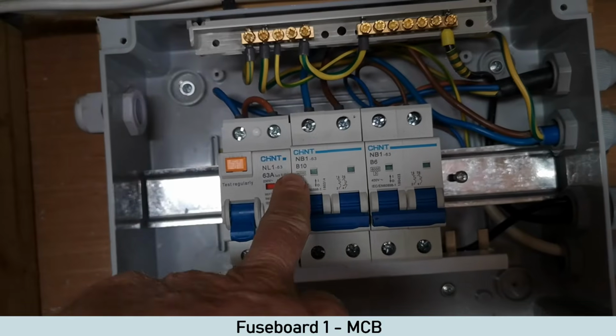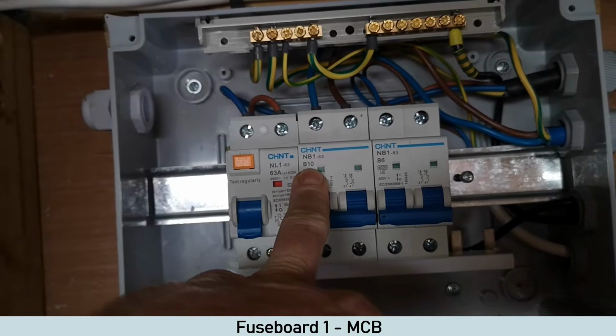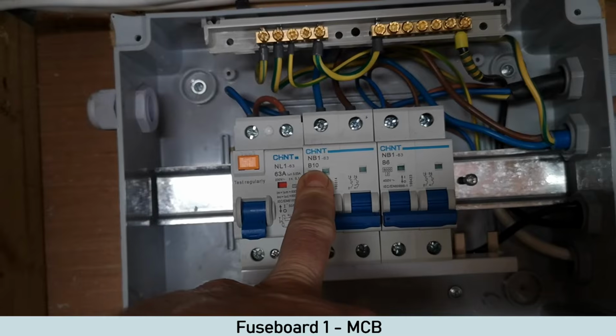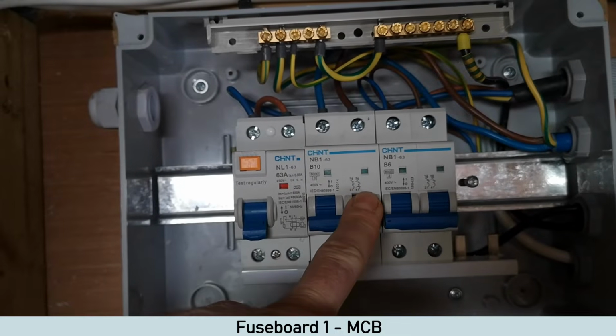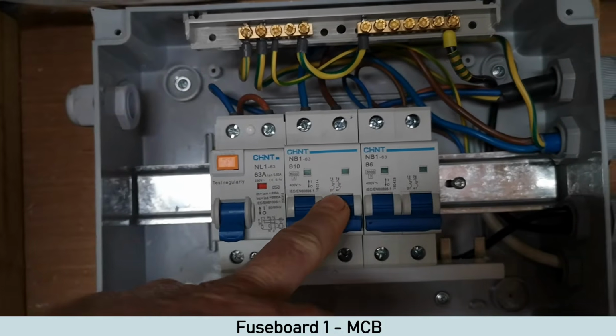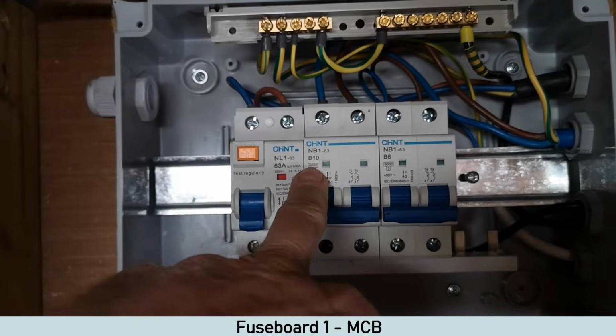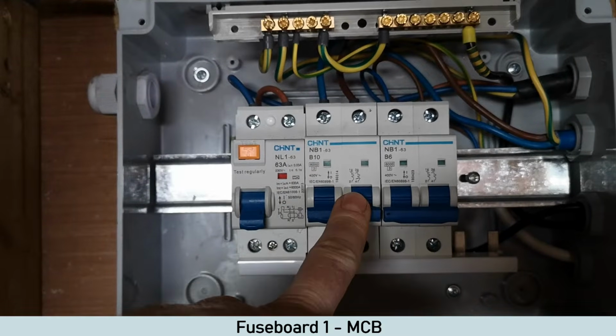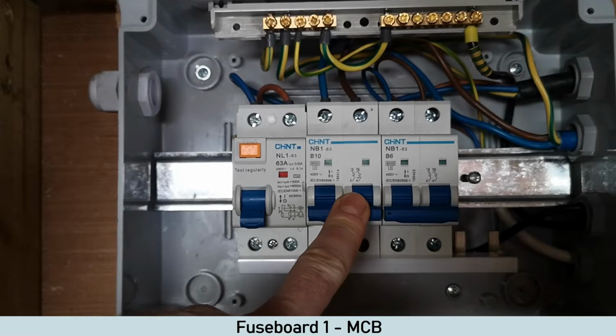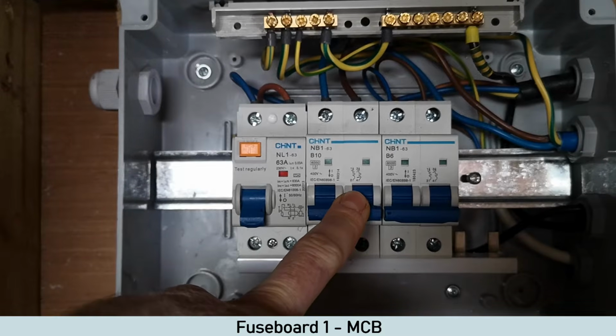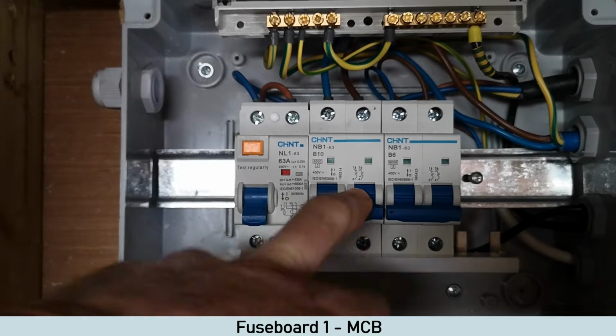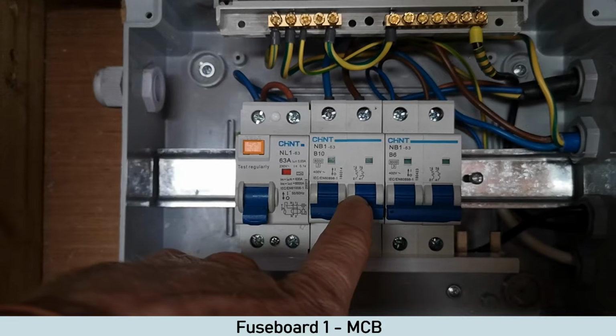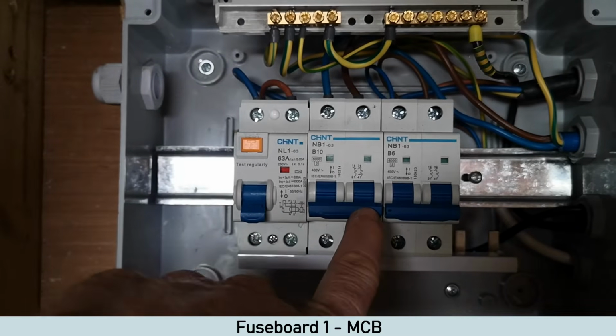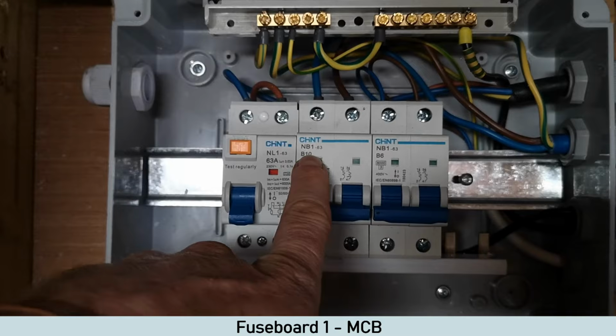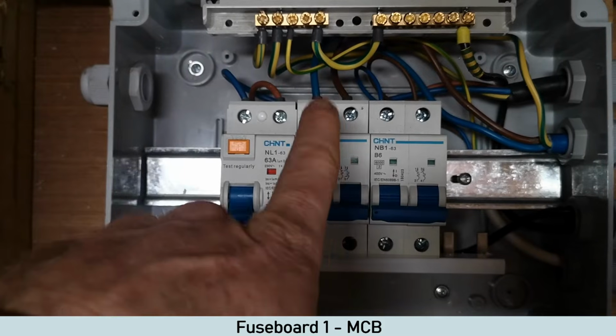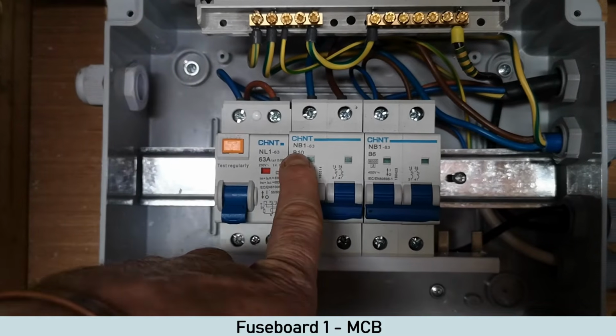This isolator, you'll notice here, it says B10. So the B is the type. Type Bs are fine for camper vans. Some people do advise type C. Now what type C is, it can withstand a higher kind of startup current. So anything that powers motors, things that have a bit of a surge on them. Type B may trip out on startup. And then the 10 is the amperage. So we have a 10 amp.